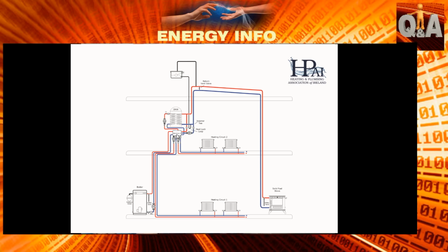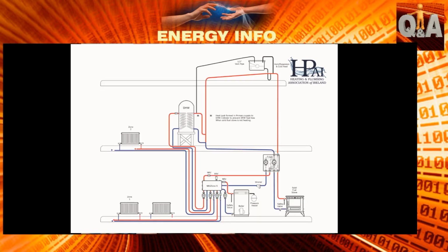Now, this is an interesting job, because if you forget the energy link for a second and follow the flow pipe up from the stove, it passes directly up, no obstruction, it has an open expansion, it has the cold feed coming underneath, it's travelling across, it passes down below the coil of the cylinder, right down to the end of the cylinder, and then there's a separate feed upwards through the coil. So we've created a sub-gravity circuit. That sub-gravity circuit heats when the first circuit heats, and now the cylinder can draw heat.